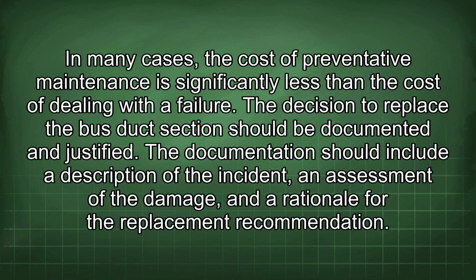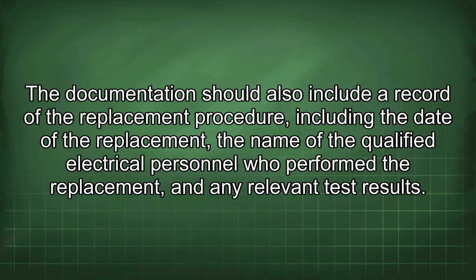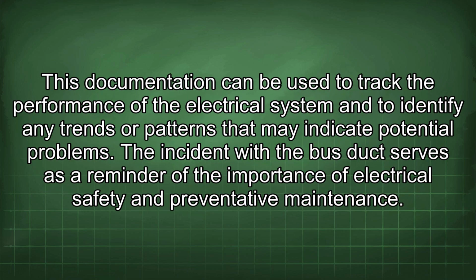The decision to replace the bus duct section should be documented and justified. The documentation should include a description of the incident, an assessment of the damage, and a rationale for the replacement recommendation. The documentation should also include a record of the replacement procedure, including the date of the replacement, the name of the qualified electrical personnel who performed the replacement, and any relevant test results. This documentation can be used to track the performance of the electrical system and to identify any trends or patterns that may indicate potential problems.